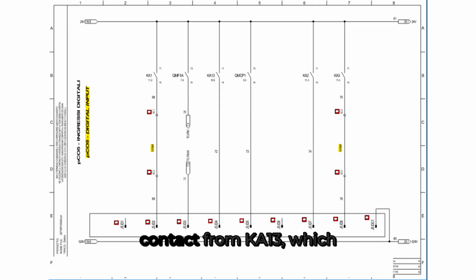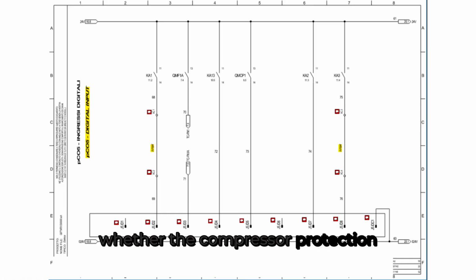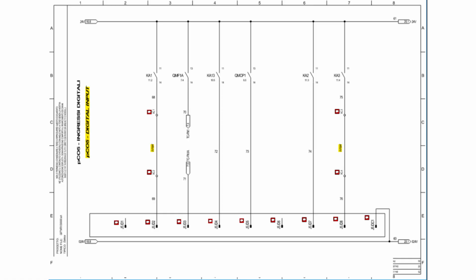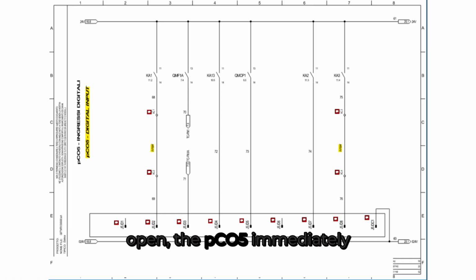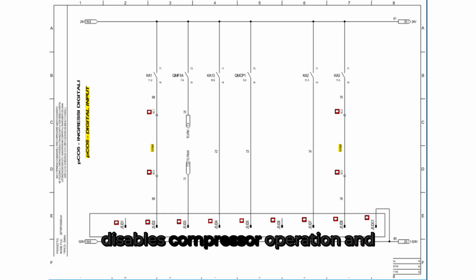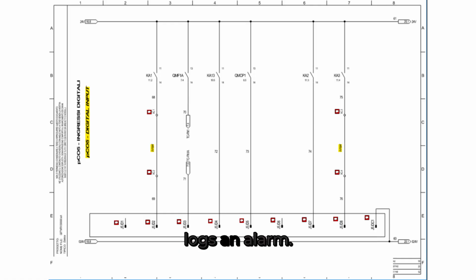Next, we have the contact from KA13, which is tied to the phase monitor. Following that, we see QMCP1, which is the compressor 1 circuit breaker feedback. Similar to the fan breaker input, it signals whether the compressor protection is intact or tripped. When this breaker is open, the pCO5 immediately disables compressor operation and logs an alarm.